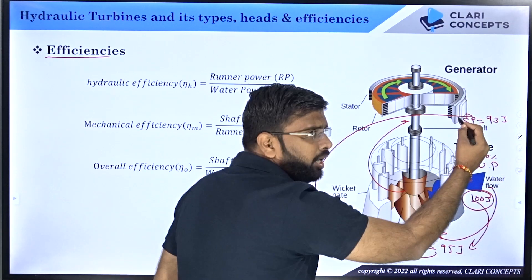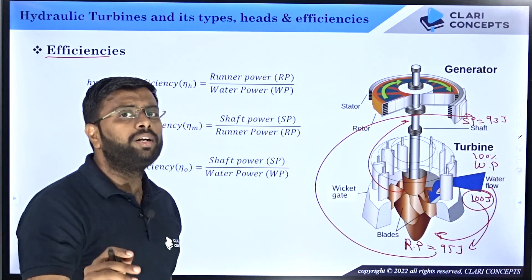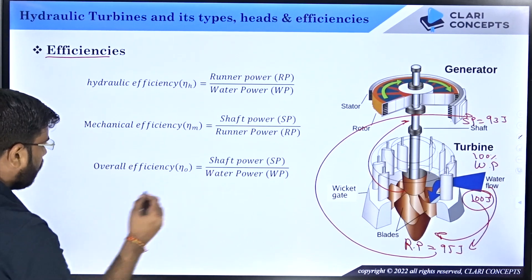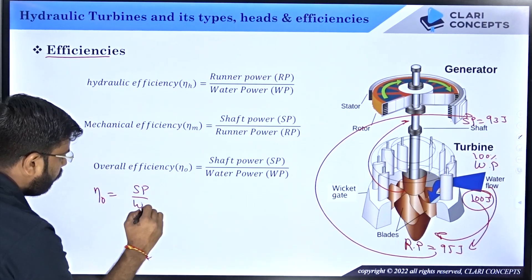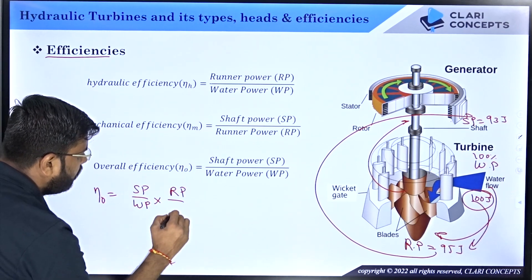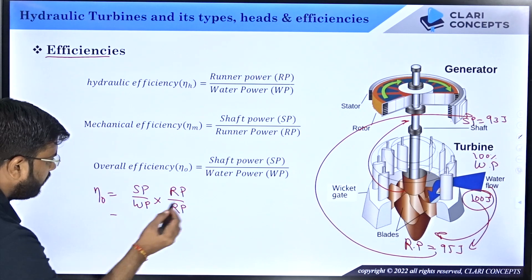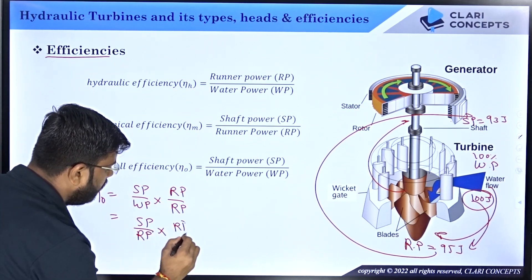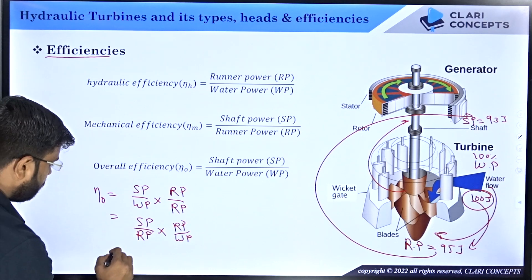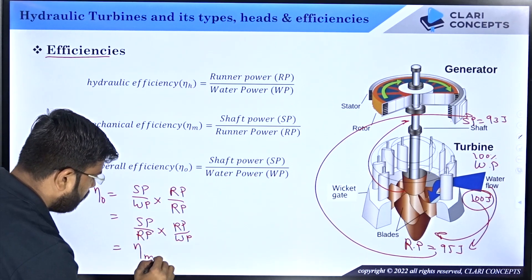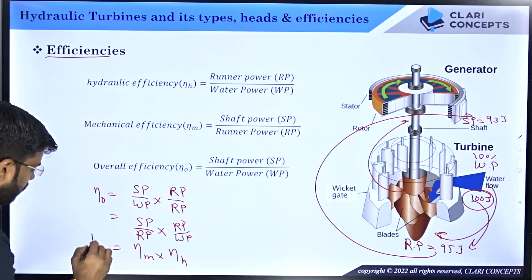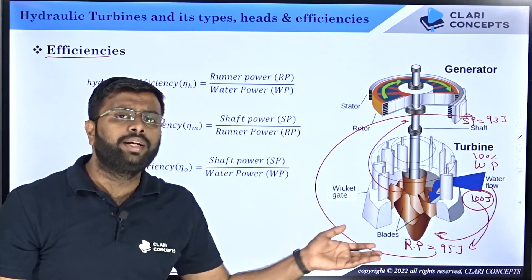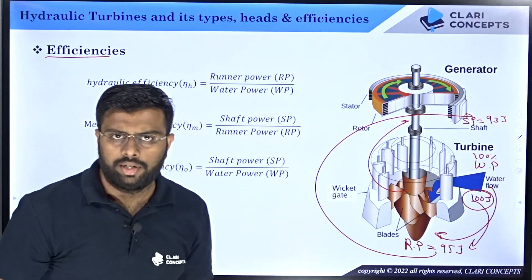The overall efficiency covers the whole process: 100 joules of water power yielding 93 joules of shaft power gives 93% overall efficiency. Overall efficiency eta_O equals shaft power divided by water power. We can elaborate: eta_O equals shaft power by water power, and by multiplying runner power in both numerator and denominator, after cancellation we get — shaft power by runner power times runner power by water power — which is mechanical efficiency times hydraulic efficiency. So overall efficiency is the product of both efficiencies.